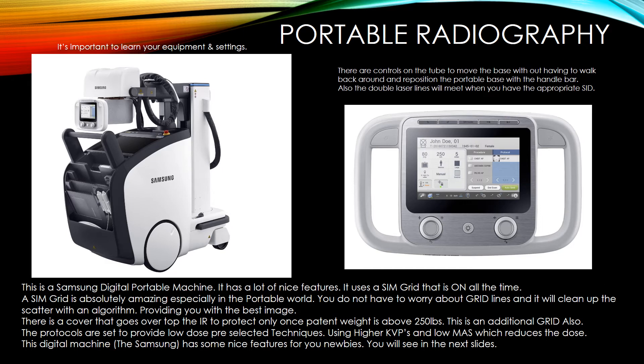In the next couple of slides you will see: if you look at the picture in the right-hand corner, you will see controls on the tube that move the base without having to walk all the way back around and reposition the portable base with the handlebar. Also look at the double laser lines — they will meet once you have the appropriate SID.